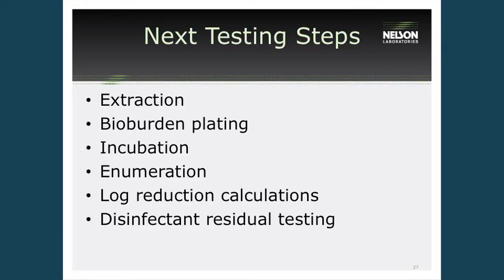This can be determined in a number of ways. It can be determined by a minimal essential media test, which is probably the quickest, easiest, and cheapest by all means. Or else we can look for the exact disinfectant that was used in the evaluation. We do this by performing a UV-vis test, and we determine the higher level of disinfectant, and then we can test for any residuals of disinfectant on the device. So this is a very important aspect of the disinfectant testing.